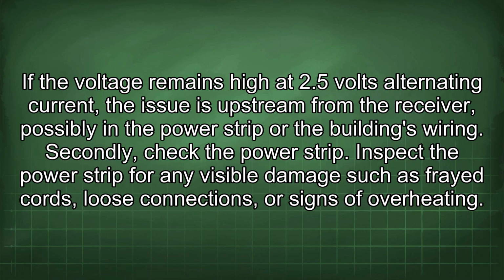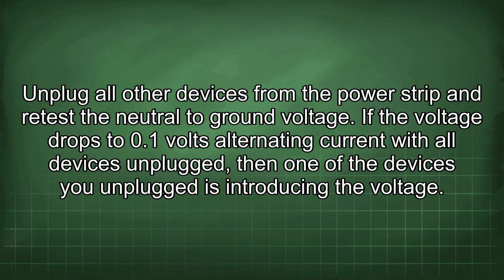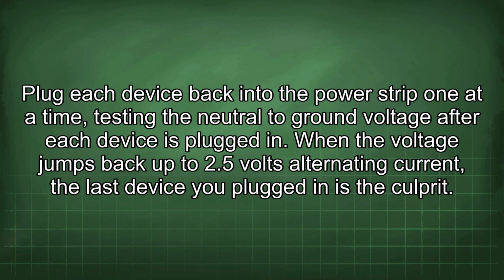Secondly, check the power strip. Inspect the power strip for any visible damage such as frayed cords, loose connections, or signs of overheating. Unplug all other devices from the power strip and retest the neutral to ground voltage. If the voltage drops to 0.1 volts alternating current with all devices unplugged, then one of the devices you unplugged is introducing the voltage. Plug each device back into the power strip one at a time, testing the neutral to ground voltage after each device is plugged in.